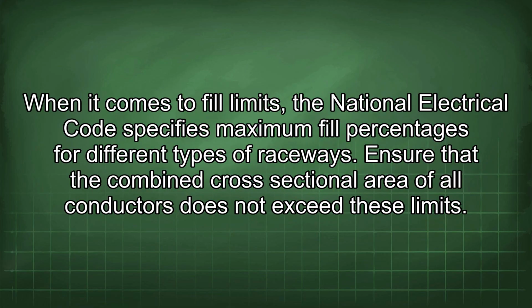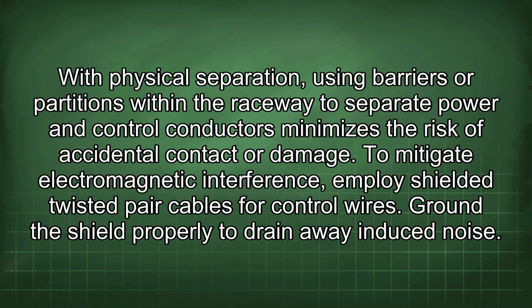When it comes to fill limits, the National Electrical Code specifies maximum fill percentages for different types of raceways. Ensure that the combined cross-sectional area of all conductors does not exceed these limits. With physical separation, using barriers or partitions within the raceway to separate power and control conductors minimizes the risk of accidental contact or damage. To mitigate electromagnetic interference, employ shielded twisted pair cables for control wires. Ground the shield properly to drain away induced noise.